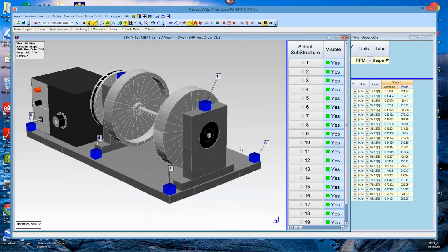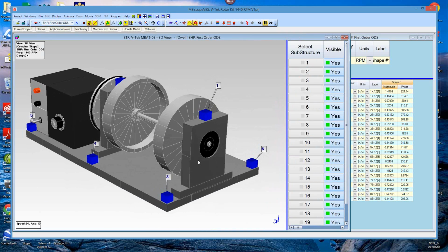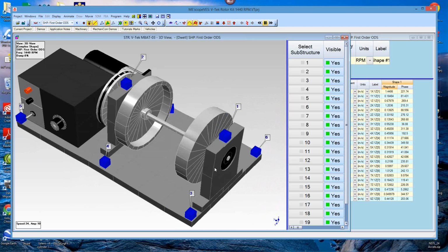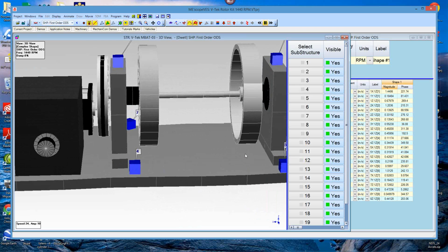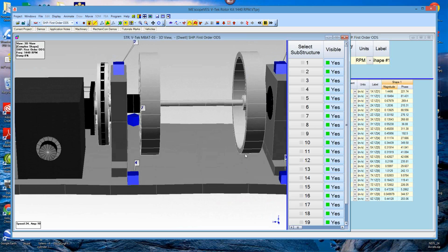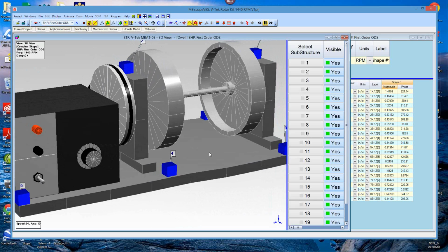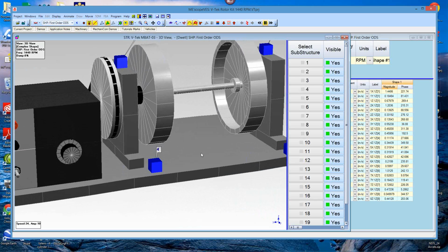But the base capability in ME'scope is to use the geometric interpolation, and it comes up with a pretty realistic picture. Certainly all these rotating points on the shafts are being animated from essentially 2 accelerometers, X, Y, Z. You can see some motion here along the direction of the shaft, let's say, the Z-axis of the shaft, and so we're getting true 3D motion, but interpolation is only going to take you so far.